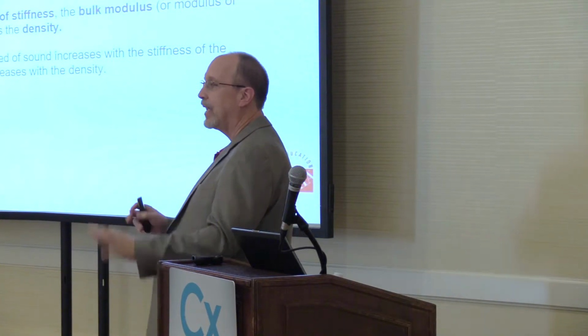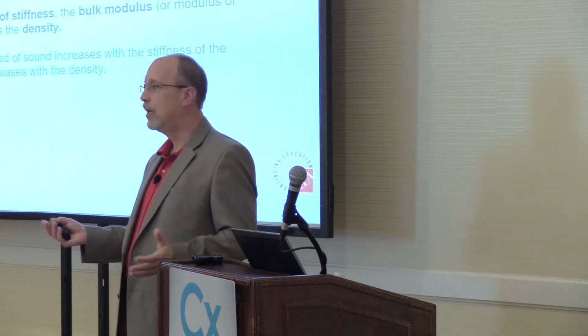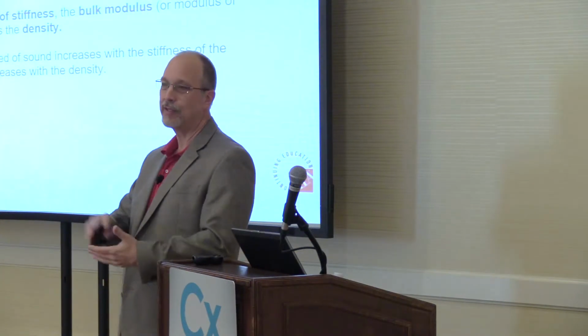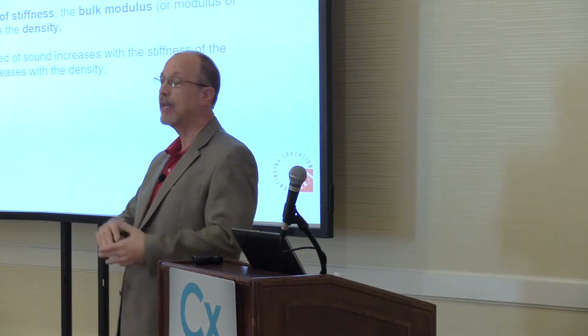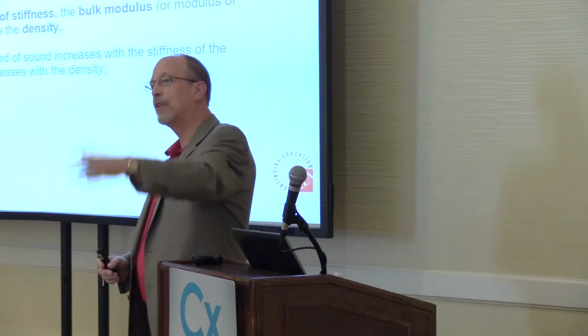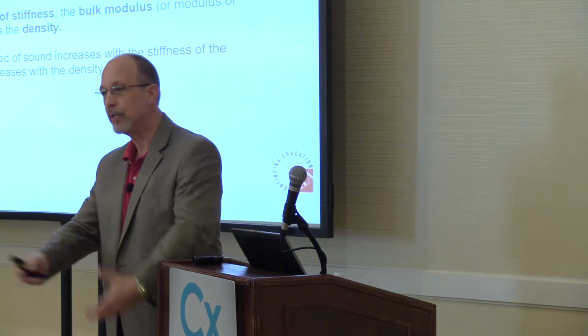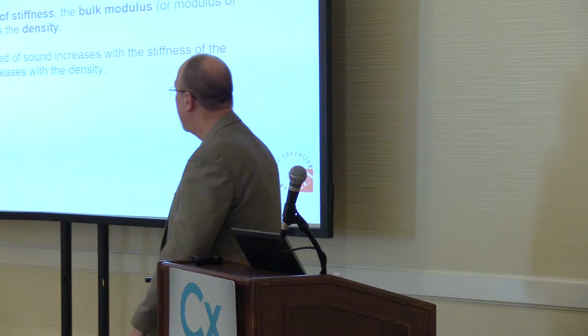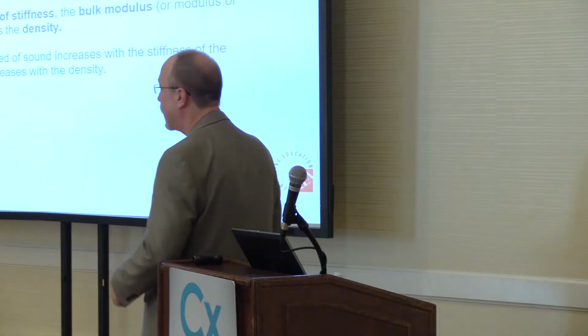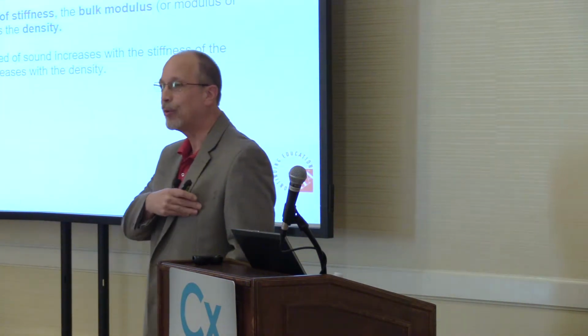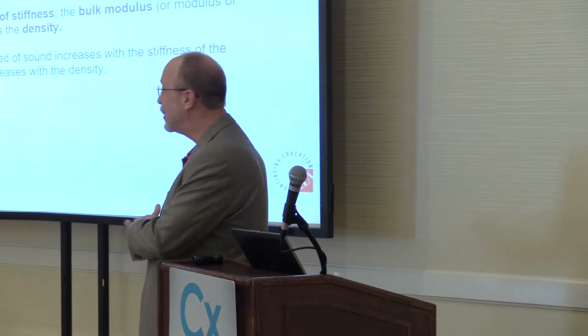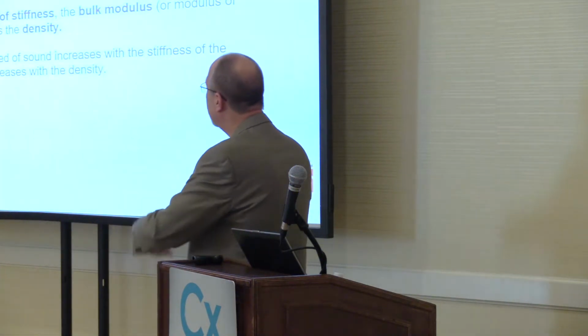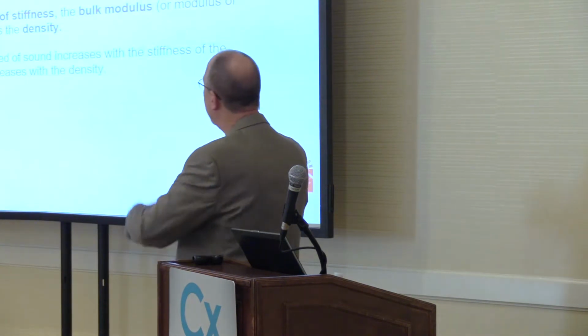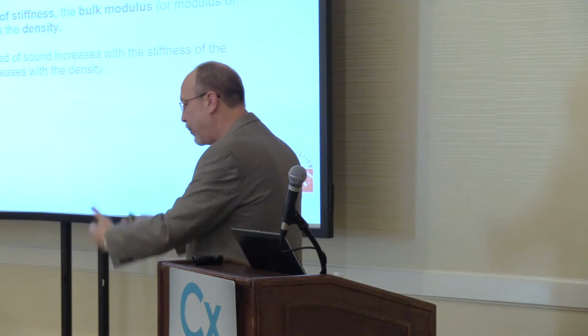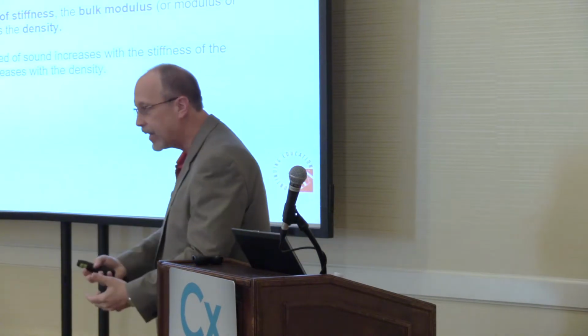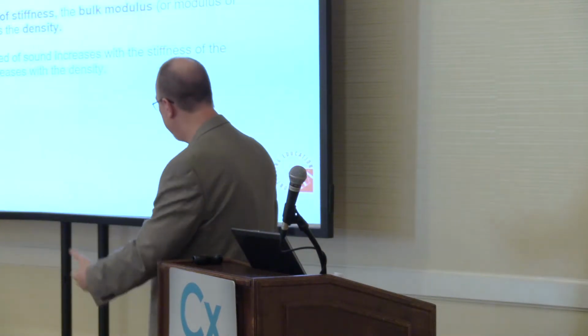If you have a new exotic chemical, then we have to do something special. We've got charts with thousands and thousands of sound speeds for exotic liquids that you guys would never see. But Dow Chemical developed something brand new, and we have to go backwards to calculate what the sound speed is. So in calculating the sound speed, I actually have a guy at my office with a real big pocket protector who likes to calculate these things out in his spare time. Sound speed involves stiffness, bulk modulus, and density. We have to go back and break down each individual product in the mixture to calculate this out.